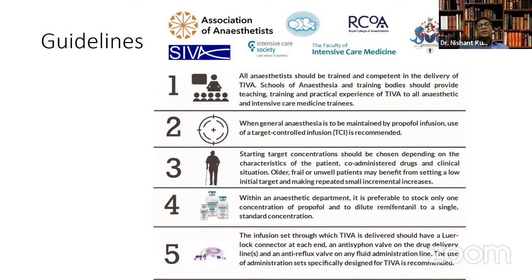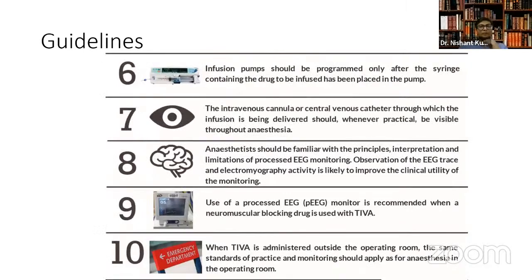Only one particular percentage, the strength of propofol, should be available. And a Luer lock connection is a must, so that there is no accidental disconnection, and it should have a one-way valve, so there is no reflux of the drug, the propofol, into the back.